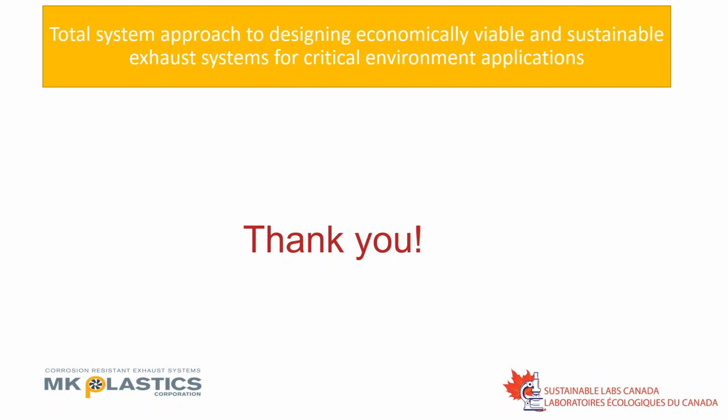I have had Aircuity systems run with our fans and our control systems. The important thing you have to understand when you're looking at something like an Aircuity system, which is working on measuring the number of air changes or the contaminants that are in the airstream, is that if the fan is not selected correctly and you have to open up your bypass damper, or in some cases, some fan manufacturers actually use bypass air constantly to provide the volume for their nozzle velocity, then your energy savings are going to be reduced accordingly. So the more you have to open up your bypass damper to accommodate what the Aircuity system is asking the fans to do, your energy saving is going to be reduced.